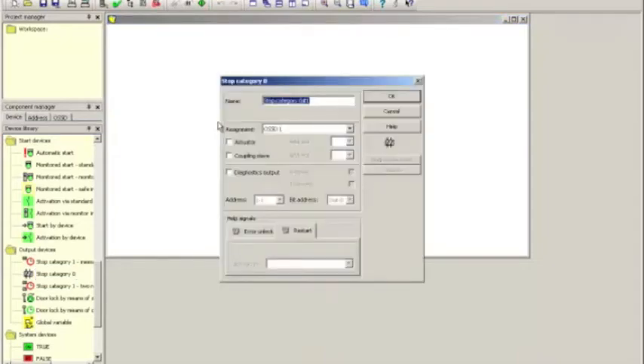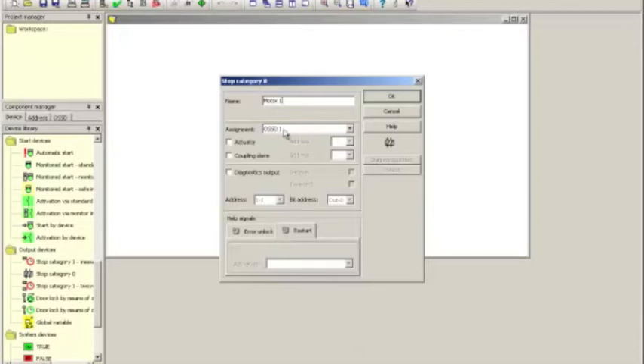On the configuration screen, we're going to start again by providing our safe output and we're going to use a stop category zero for immediate shutdown. Once that has been dragged and dropped onto the configuration space from the device library, the details window pops up and a name can be put in. Here on the assignment window and the assignment part, we select OSS-D1 because on the setup that I have put together, the motor contactor is controlled by the first safe output and that's called OSS-D1. No further changes needed here. Click OK.